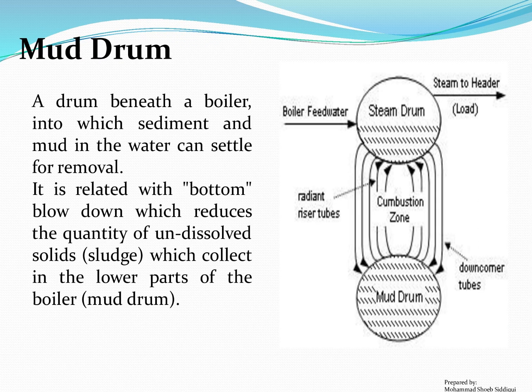Mud drum. A drum beneath a boiler, into which sediment and mud in the water can settle for removal. It is related to bottom blowdown, which reduces the quantity of un-dissolved solids and sludge which collect in the lower parts of the boiler mud drum.